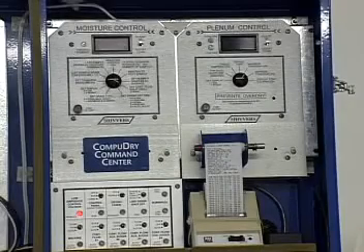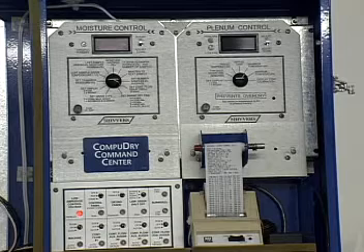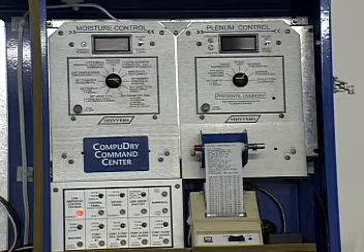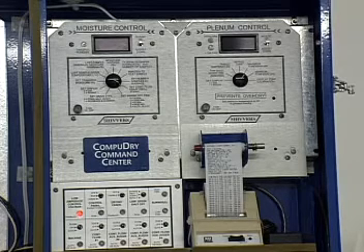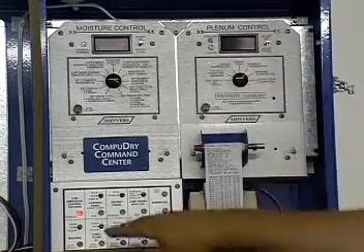Now that you've learned the moisture control and the plenum control and all the toggle switch settings, we're going to do a basic startup showing you how to operate the plenum control side without the moisture control side running, because you have wet corn that you're starting the season off with, and I need to get it pre-dried. So we're going to do a pre-dry with the plenum control right from the start.